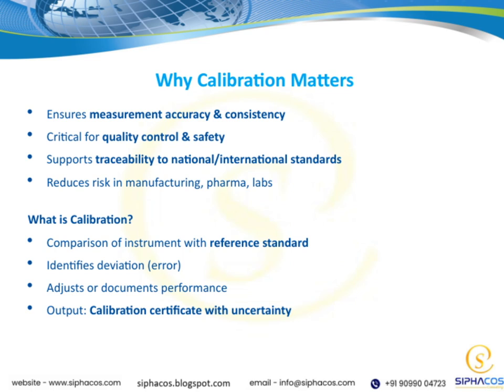Now, you might be wondering, what exactly is calibration? It's essentially a comparison process where we check an instrument against a reference standard that is known to be accurate. This comparison helps us identify any deviations or errors in the instrument's performance. If we find discrepancies, we can then adjust the instrument or simply document how it's performing. The key output of this process is a calibration certificate, which not only confirms that the instrument is working properly, but also includes the measurement uncertainty, giving us confidence in the results we rely on daily.